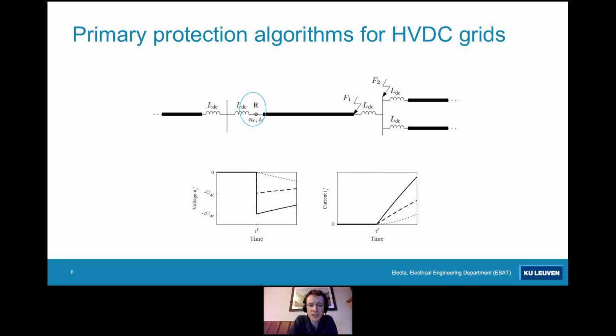Now, for this fault discrimination, we could make use of the weakness of a DC circuit breaker. Each DC circuit breaker requires a series inductor to limit the rate of rise of the fault current. So it has a maximum interruption capability. And if we don't limit the rate of rise of the fault current, even within the 2 millisecond opening time, the fault current would exceed the breaker capacity. Now, this series inductor also offers a means to discriminate faults at both sides of these inductors, because they act as a low pass filter combined with the cable.